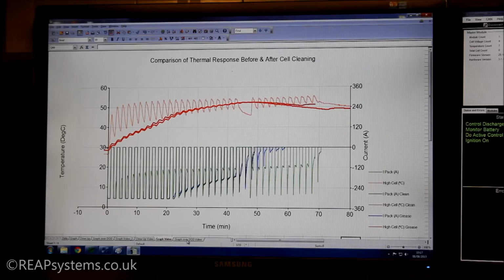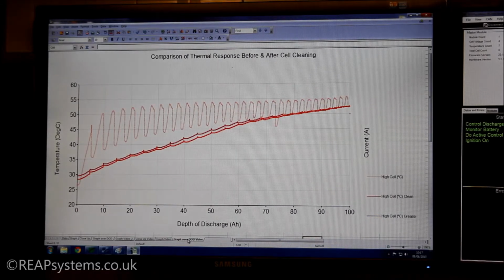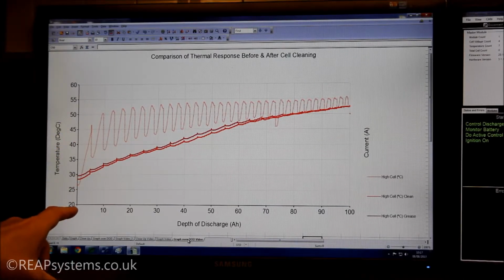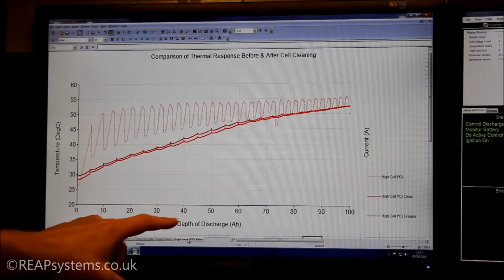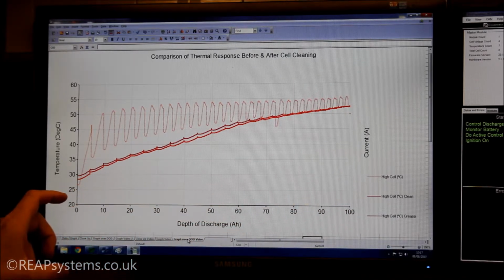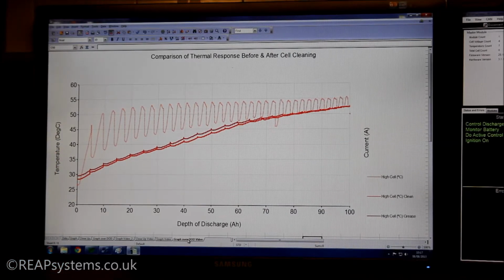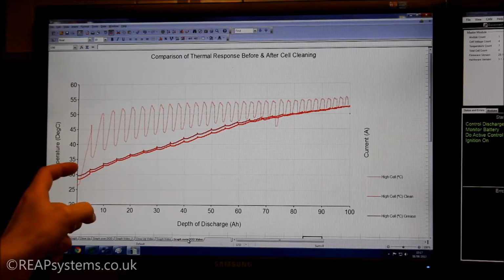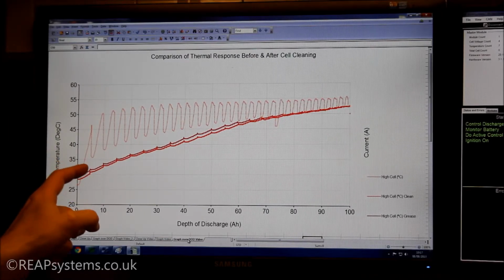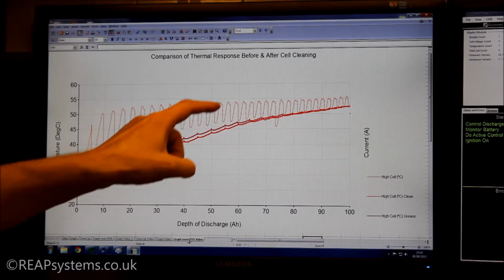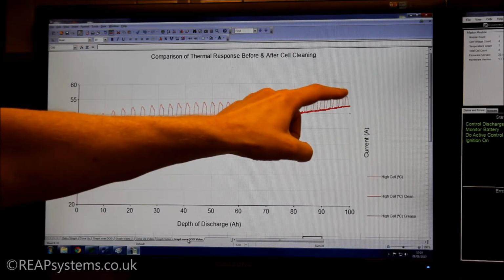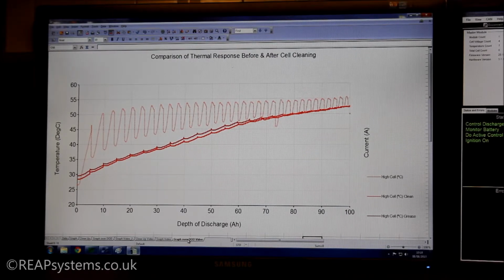So, what are the temperatures doing across the test? This shows the behavior of the temperatures quite nicely. Here, instead of using time on the x-axis, we use the depth of discharge. And so what is this telling us? Well, it's showing us that the unclean terminals have a much higher change in temperature, and then it stabilizes at its highest level for most of the test, where the BMS is reducing the allowable discharge current. And it takes much longer for the cleaned or greased terminals to reach that final temperature, and that's only towards the end of the test.